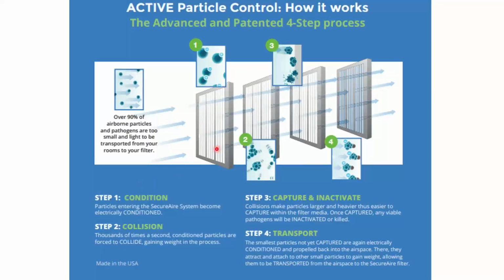What ends up happening is the airflow comes through the first piece, which is a conditioner. That charges particles, some positive and some negative, and those things collide into each other and get larger because of that. The positive and negative attract, and now instead of five small things, it's one larger thing, which is more likely to get caught in the filter right after that.